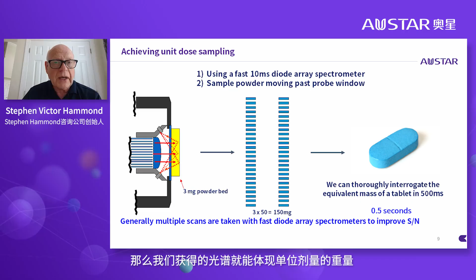And the way we get around this problem of a small amount of material contributing to an individual scan is in fact to take multiple scans while the powder is moving, which of course it is in a continuous system, and to average the signal we get from, say, 50 scans. Now, the spectrometer is very fast scanning. It can collect a scan in 10 milliseconds. So it doesn't take long to do this. So that's the approach that's been taken. We scan multiple times with the powder moving, so the powder is refreshed in front of the probe as we take the 50 scans. And by integrating those 50 scans together, we can say the spectrum that we're getting represents a unit dose weight.